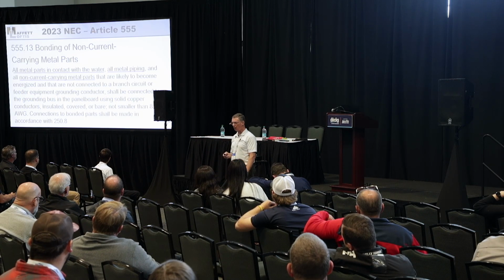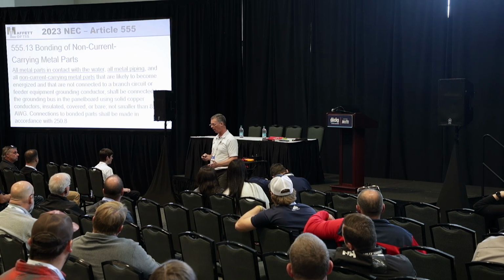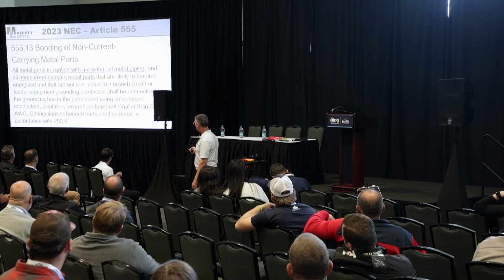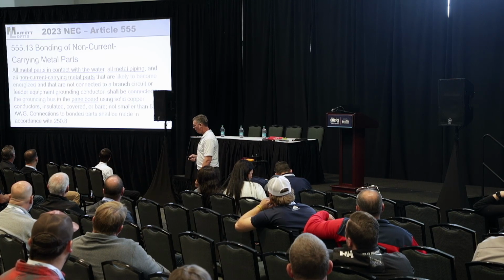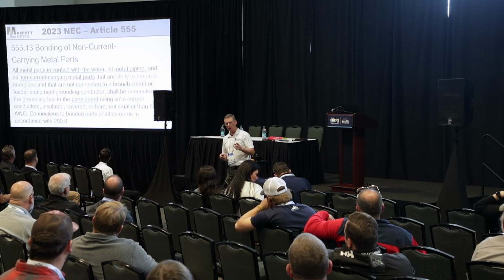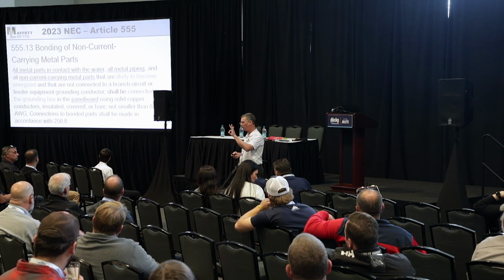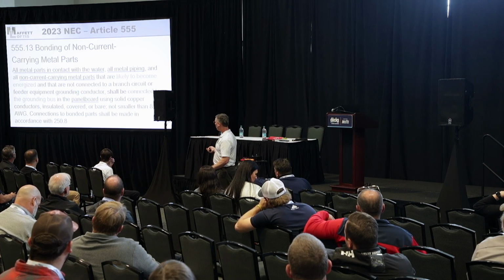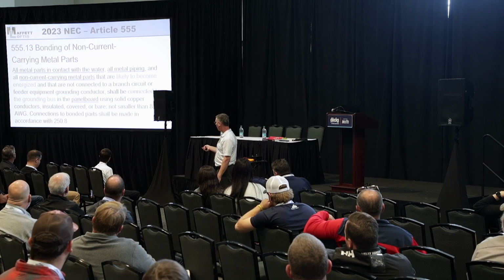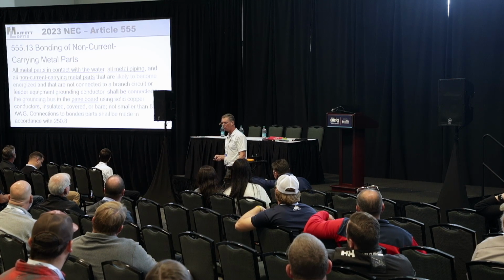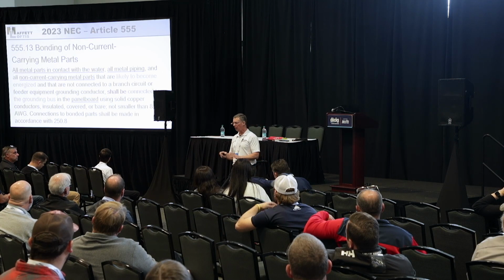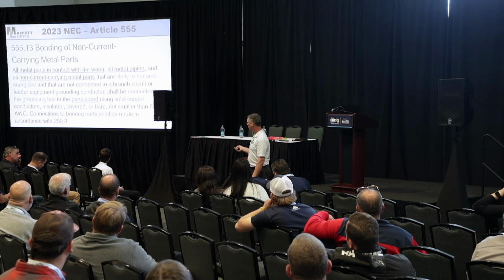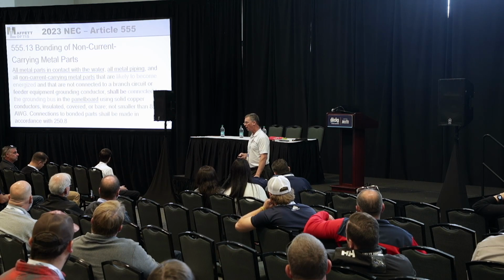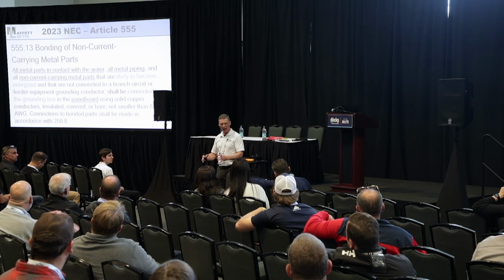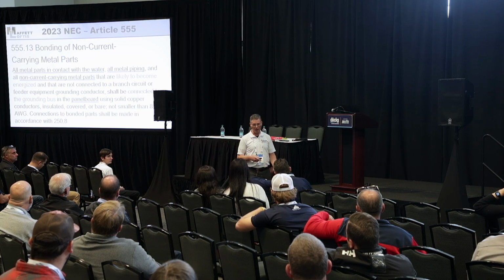But the issue is, and this was probably a language issue, not the intent of the code-making panel, that it says all these 3 are bonded if likely to be energized. By interpretation from some electrical inspectors, likely to be energized applies only to that 3rd piece of metal and does not apply to the previous 2. So what they're saying is that any metal in contact with water has to be bonded to the grounding bus of a panelboard. And that's a problem, because if you have metal spud poles, how do you bond a metal spud pole? It's in contact with the water. And that's my argument.